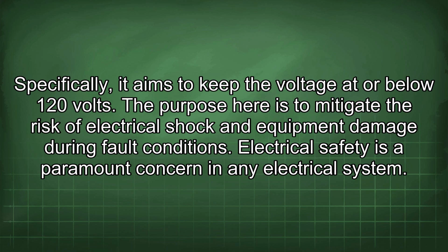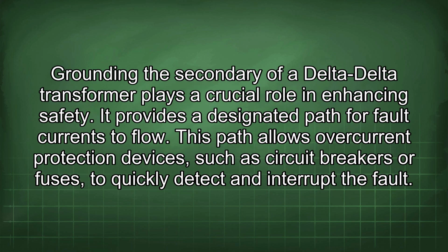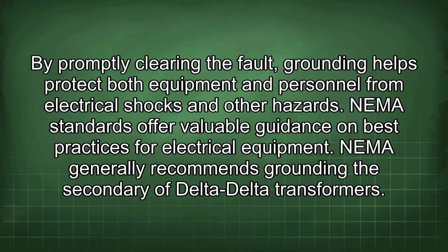Electrical safety is a paramount concern in any electrical system. Grounding the secondary of a delta-delta transformer plays a crucial role in enhancing safety. It provides a designated path for fault currents to flow. This path allows overcurrent protection devices, such as circuit breakers or fuses, to quickly detect and interrupt the fault. By promptly clearing the fault, grounding helps protect both equipment and personnel from electrical shocks and other hazards.